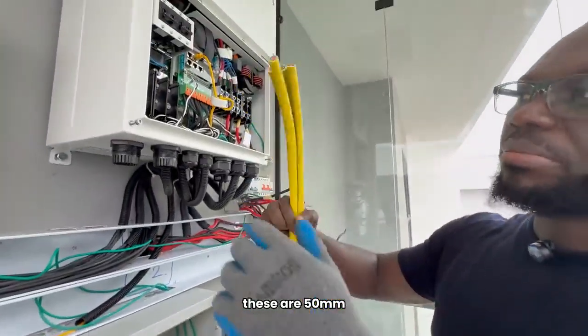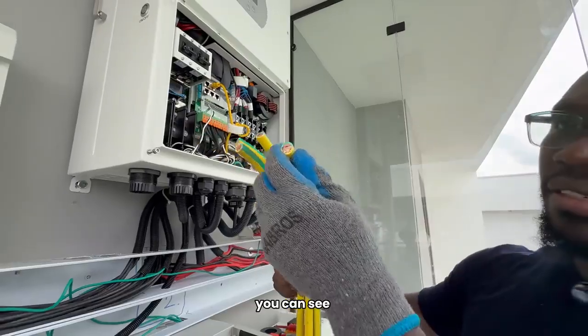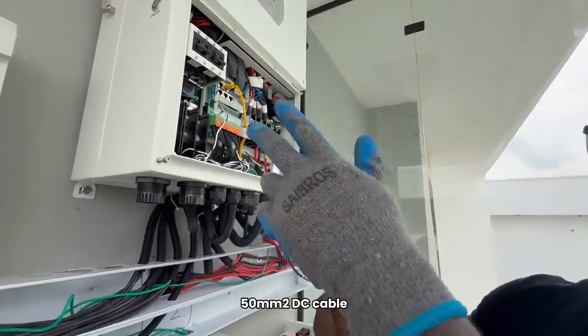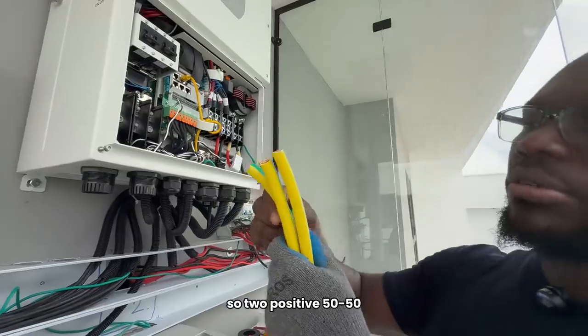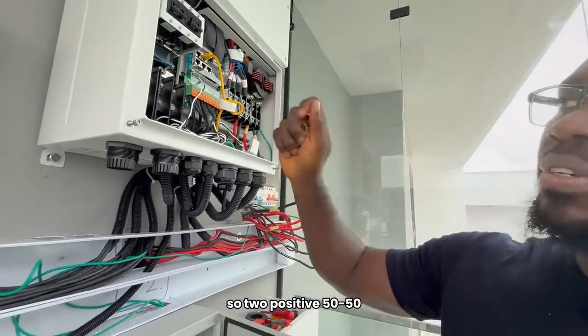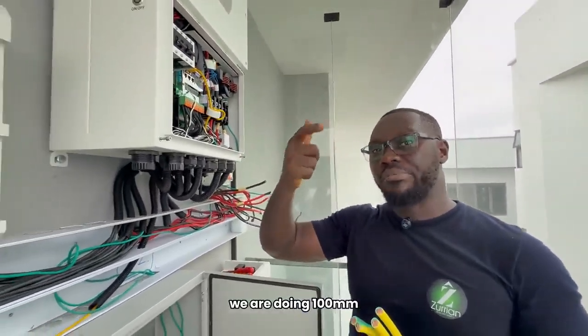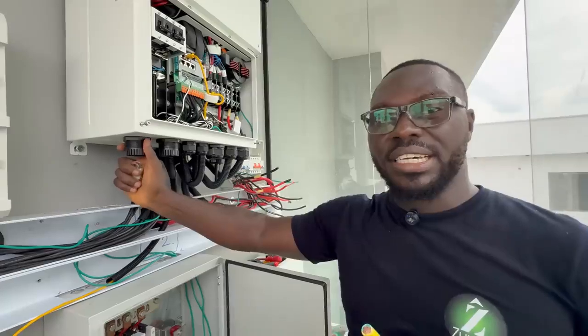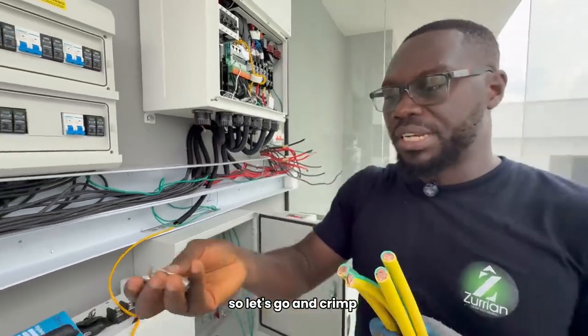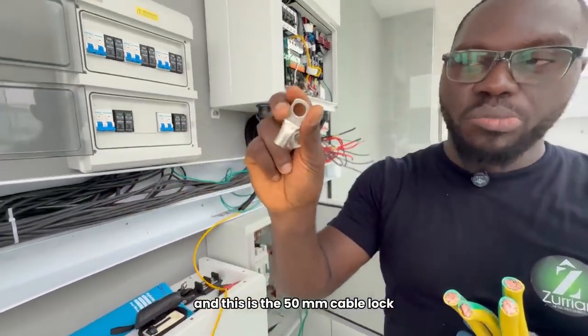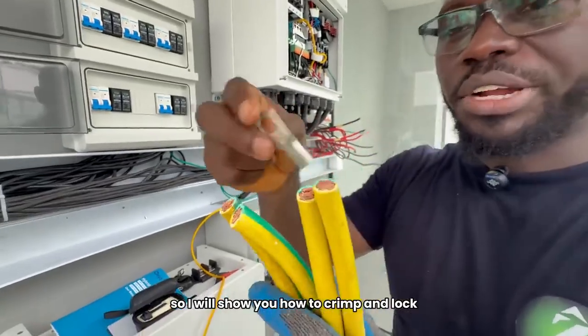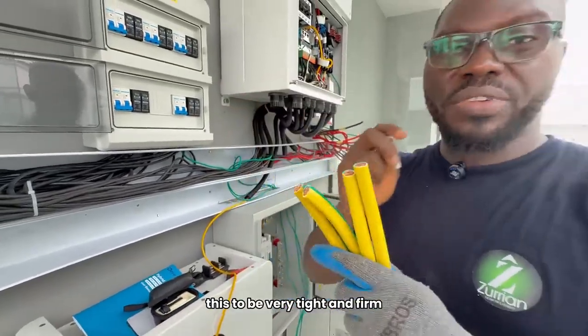To do that, these are 50 mm square DC cables. Two positive, 50-50, two negative, 50-50. So automatically we're doing 100 mm so it can carry the current. Let's go crimp. This is the 50 mm cable lug, and I'll show you how to crimp and lock it to be very tight and firm.